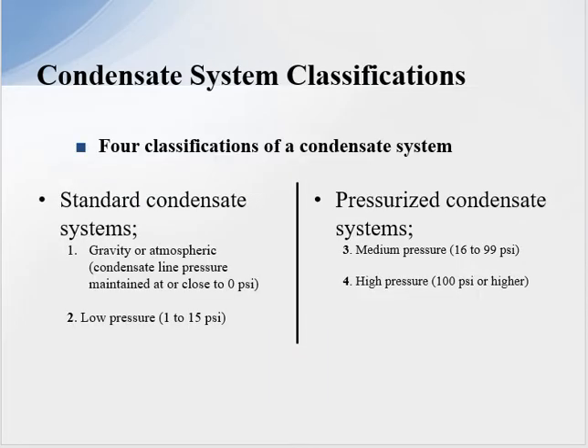When looking at a condensate system, we have to do the classifications. There are four classifications: one is a standard condensate system, which is gravity or atmospheric — condensate line pressure maintained at or close to zero PSI, which is very important on many process applications. The second is low pressure, one to fifteen PSI. Today's technology also includes pressurized condensate systems operating at sixteen to ninety-nine PSI for medium pressure, and high pressure over one hundred PSI.